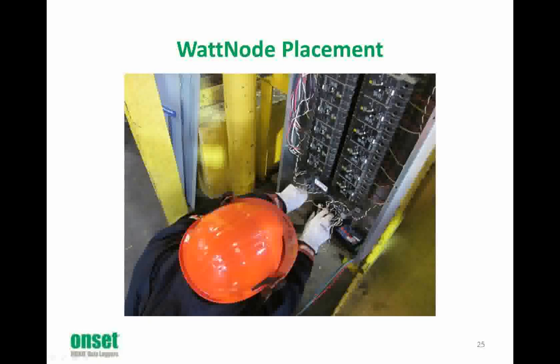Now that we've identified the voltage we're working with, we will be metering. We must determine a safe location for our equipment. The location must be large enough to accommodate the equipment, free from sharp edges and moving parts, and easily accessible for both safe installation and removal. An ideal location is one that has minimal impact on the safe operation and maintenance of the equipment. The best location for a WattNode is typically at the bottom interior of the electrical panel, as we can see here in this photo.